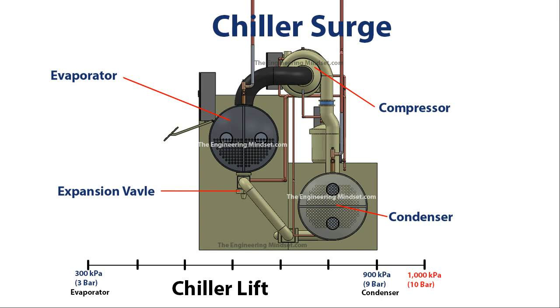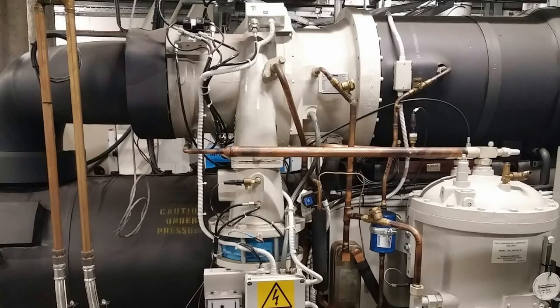You'll know when this occurs because the chiller is going to make a really loud groaning or squealing noise coming from the compressor. You'll probably also experience some quite large swings in the amount of amps being drawn by the compressor. The sound of a surging chiller includes a sudden increase followed by a sudden drop — that's where the pressure re-equalizes — then it rises again and there's another sudden drop.